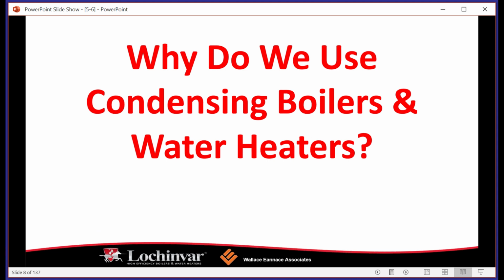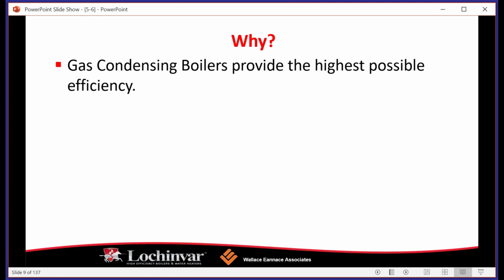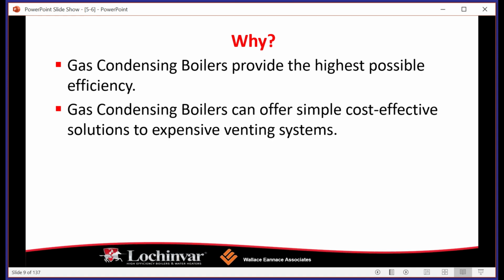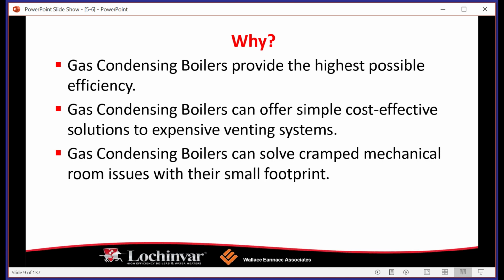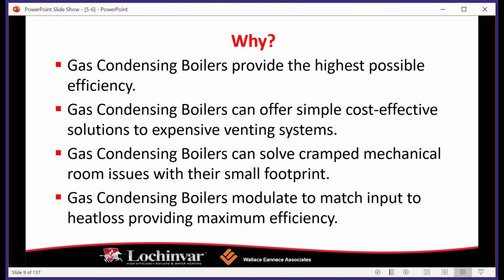So first off, we're going to say, why do we use condensing boilers and water heaters? And moreover, what does that mean? Why do we use that? So a condensing boiler and a water heater are going to have some distinct advantages over what we're going to say is a standard efficiency AFUE piece of equipment. So gas condensing boilers and water heaters provide the highest possible efficiency. They offer simple, cost-effective solutions to expensive ventings. And we're going to cover that in a lot more depth in a couple slides. Cramped boiler room issues with a small footprint, and then modulate to match the boiler input. So let's start from the top.